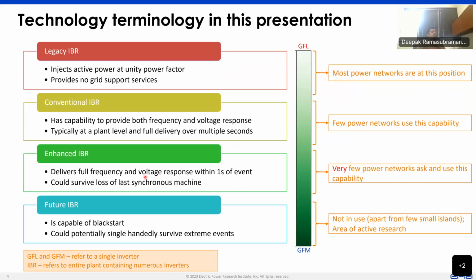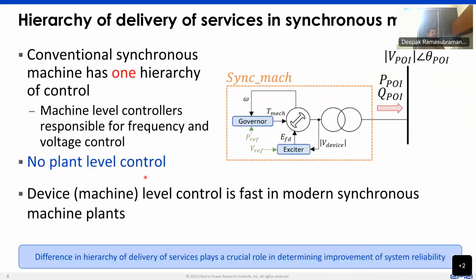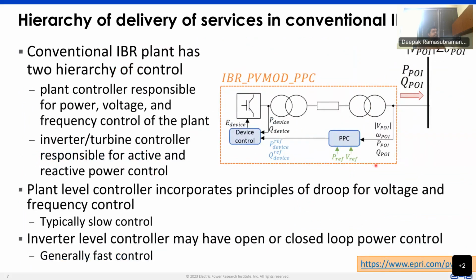Slide 4. So a PV plant that is connected today, and actually it might be beneficial to talk about this: the conventional inverter plant that is connected today is able to provide voltage and frequency response primarily due to its power plant controller. The power plant controller looks at the voltage at the POI and evaluates the frequency at the point of interconnection. It usually utilizes droop loops, or droop characteristics, inside the power plant controller, and translates that information down to the device-level control and changes the P and Q reference of these devices.